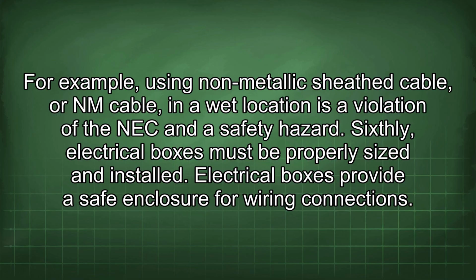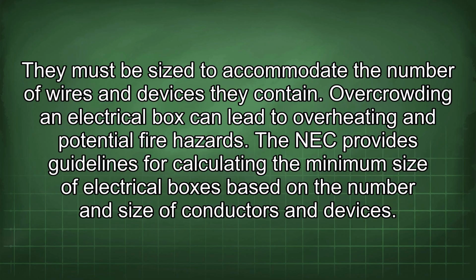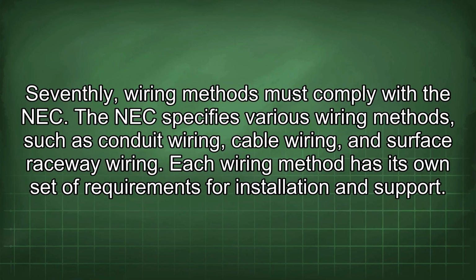Sixthly, electrical boxes must be properly sized and installed. Electrical boxes provide a safe enclosure for wiring connections. They must be sized to accommodate the number of wires and devices they contain. Overcrowding an electrical box can lead to overheating and potential fire hazards. The NEC provides guidelines for calculating the minimum size of electrical boxes based on the number and size of conductors and devices.